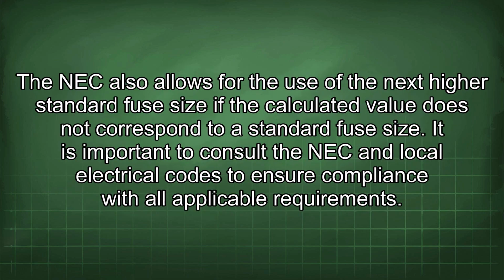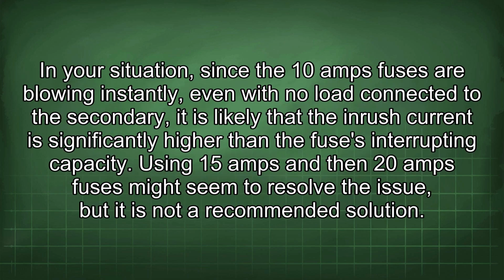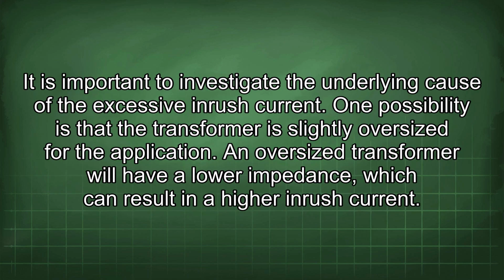The NEC also allows for the use of the next highest standard fuse size if the calculated value does not correspond to a standard fuse size. It is important to consult the NEC and local electrical codes to ensure compliance with all applicable requirements. In your situation, since the 10 amp fuses are blowing instantly, even with no load connected to the secondary, it is likely that the inrush current is significantly higher than the fuse's interrupting capacity. Using 15 amp and then 20 amp fuses might seem to resolve the issue, but it is not a recommended solution. It is important to investigate the underlying cause of the excessive inrush current.